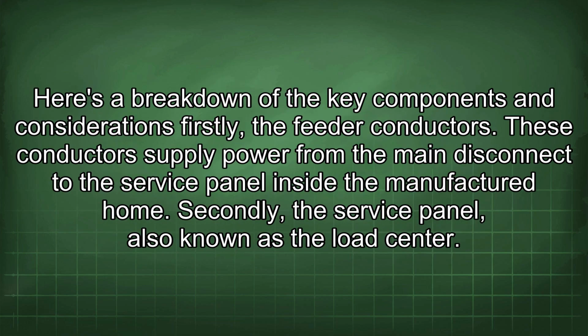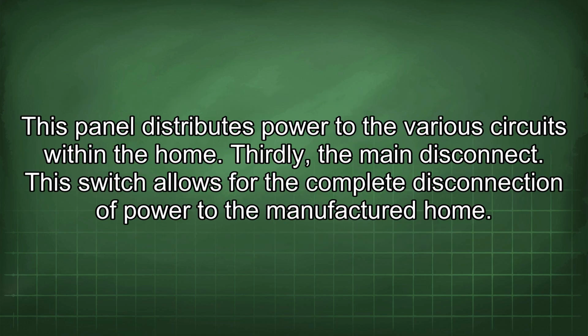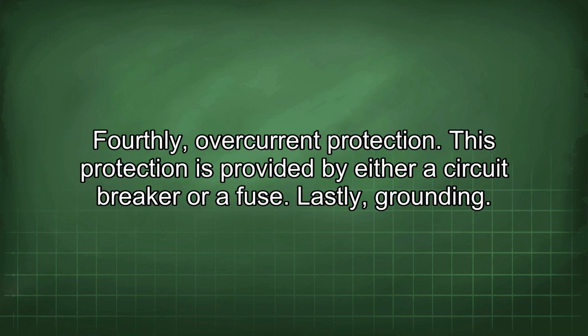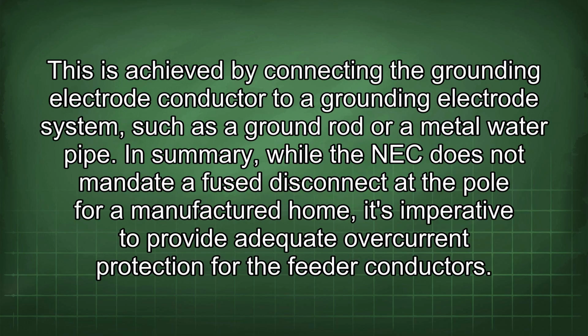Here's a breakdown of the key components and considerations. Firstly, the feeder conductors. These conductors supply power from the main disconnect to the service panel inside the manufactured home. Secondly, the service panel, also known as the load center. This panel distributes power to the various circuits within the home. Thirdly, the main disconnect. This switch allows for the complete disconnection of power to the manufactured home. Fourthly, overcurrent protection. This protection is provided by either a circuit breaker or a fuse. Lastly, grounding. This is achieved by connecting the grounding electrode conductor to a grounding electrode system, such as a ground rod or a metal water pipe.